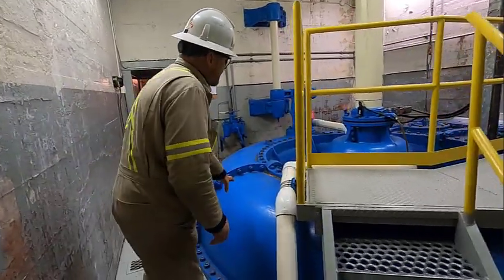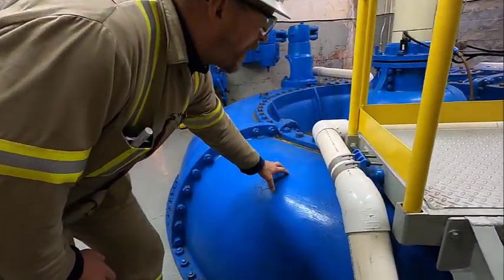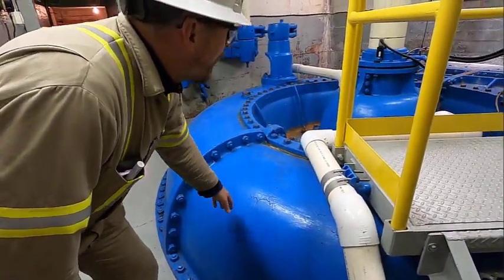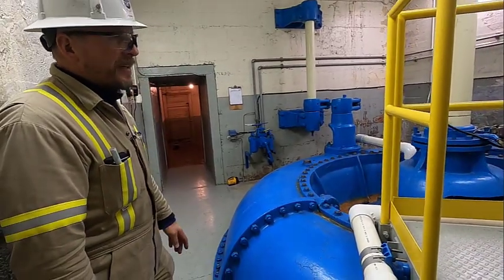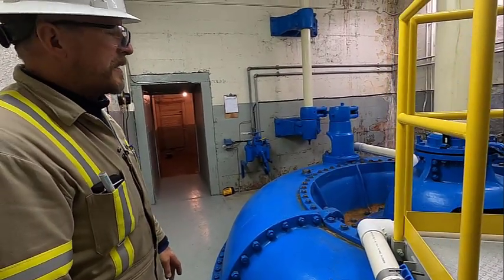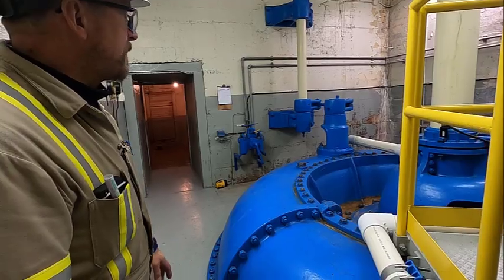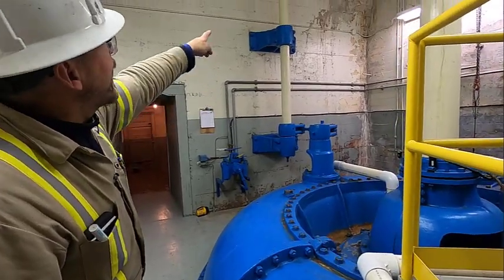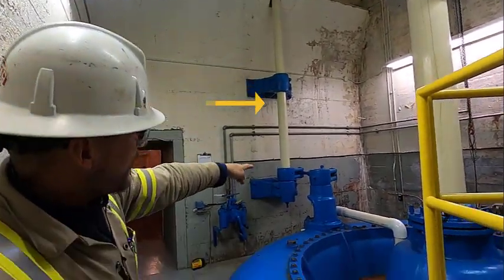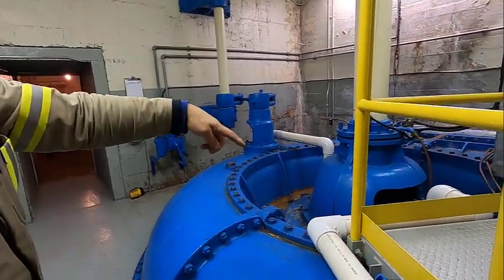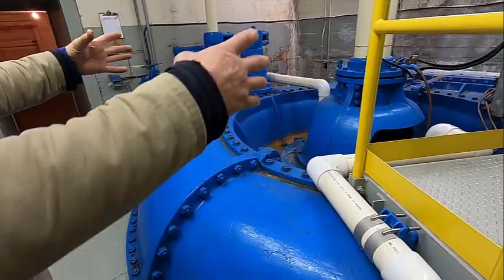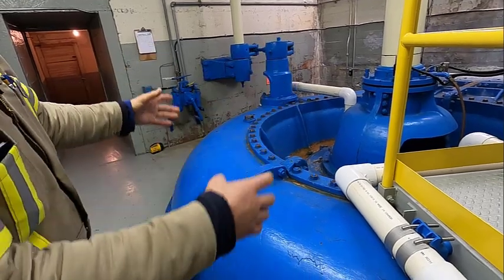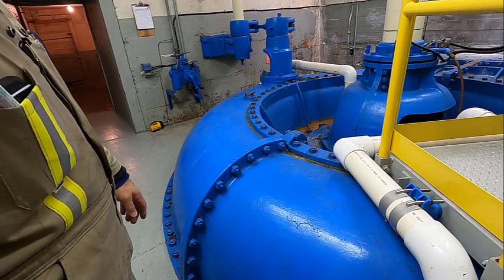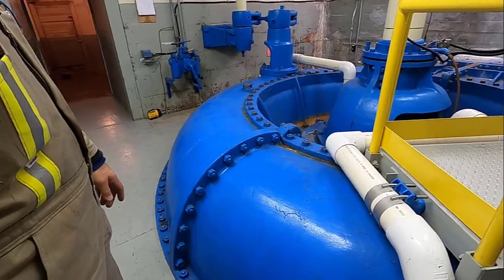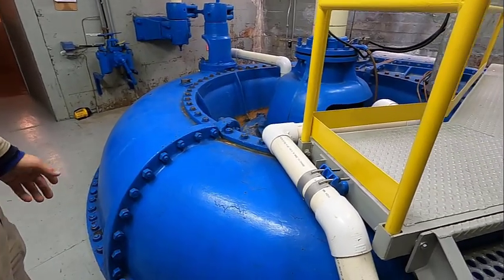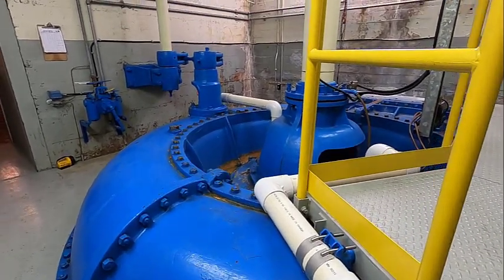So inside this is the water, again under pressure from up the forebay, and again this unit is not running. This is a standby unit, so it's just sitting here stopped. Off to the side again is the governor shaft, connecting it to the linkage. The linkage on this unit, all the linkage is inside, actually in water. It's a little bit more difficult to maintain, but it still works pretty good for a unit made in 1910.